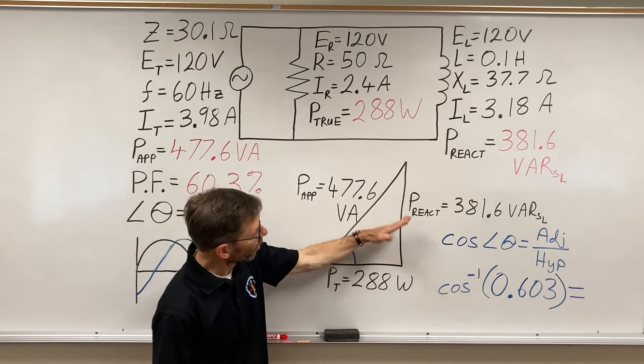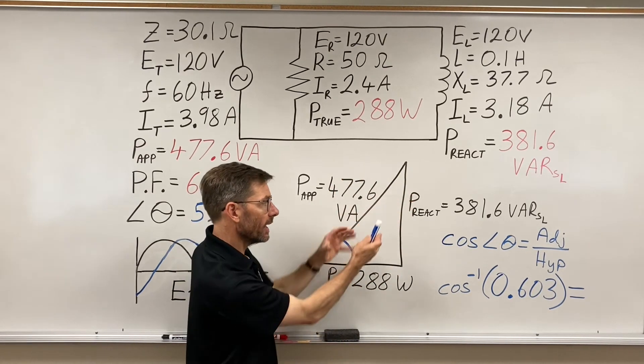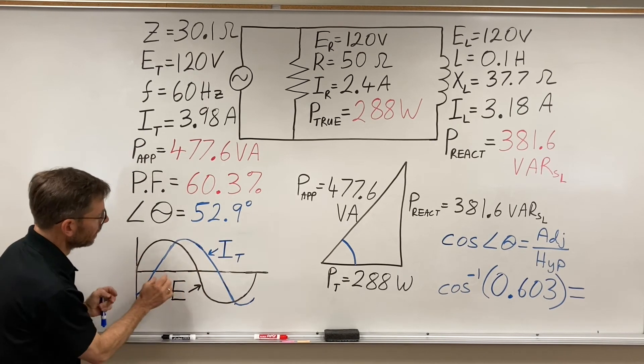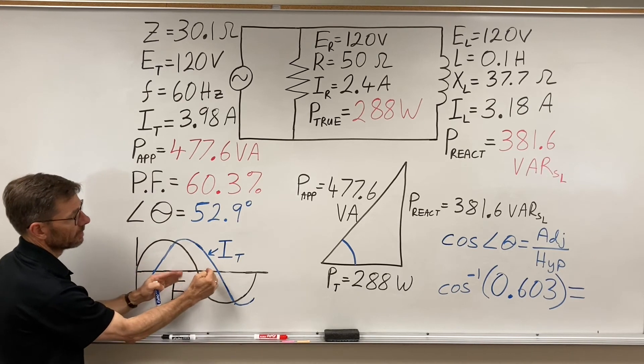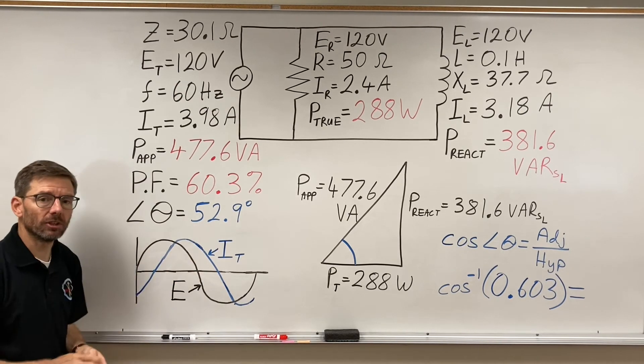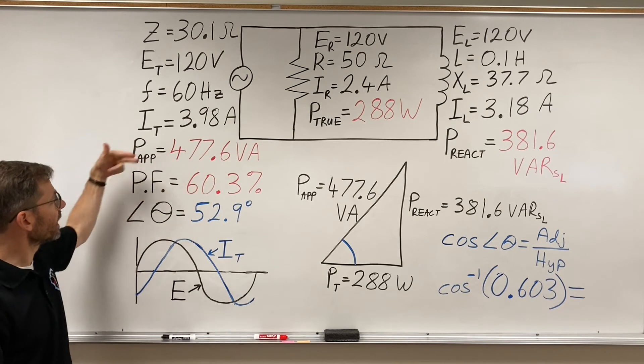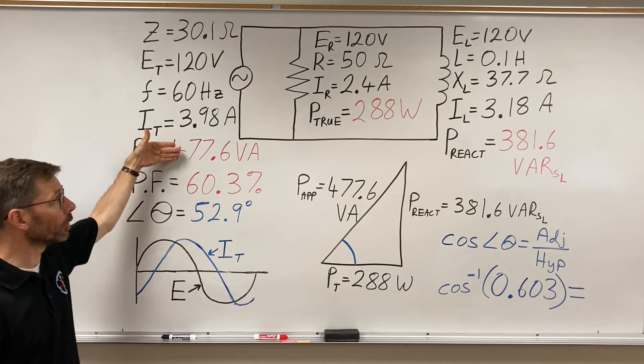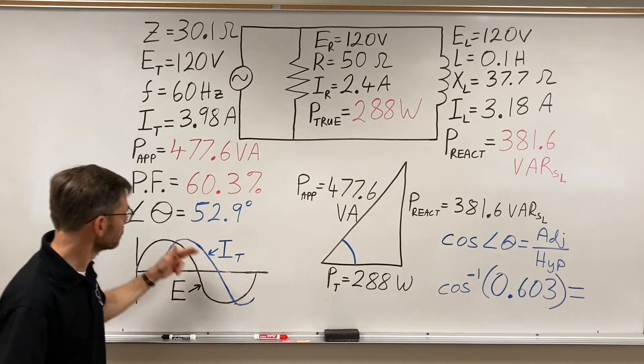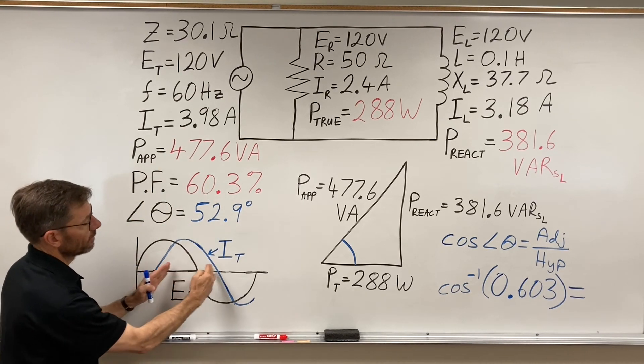And what do you get? 52.9 degrees — that's the angle. We can tell it's going to be more than 45 because the VARs side is longer than the watts side; if they were equal, it would be 45. So we can guess whether it's less than or more than 45, and sure enough, it's a little more. Back on the waveform, the total current is shifted 52.9 degrees — the current is lagging the voltage. And there we have it: our power numbers and how they relate to power factor and angle theta.